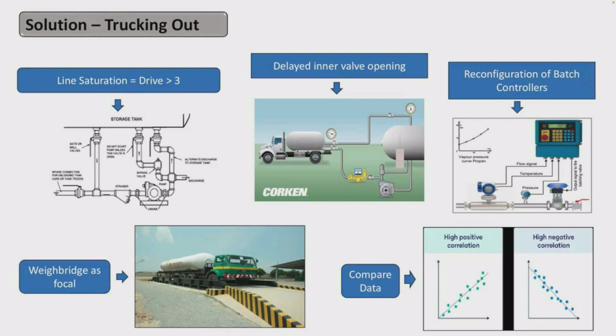So at the gantry, what we did is, since we have vapor going into our Coriolis, luckily we have a liquid return line. In case you're loading a truck and it's leaking, what happens? You can't discharge a leaking truck out of your terminal - you can't, it will come back to you, and NMDPRA will follow you. So what we do is make sure we discharge all of that truck and all the product in the leaking truck back to our tank. So we have a liquid return line.